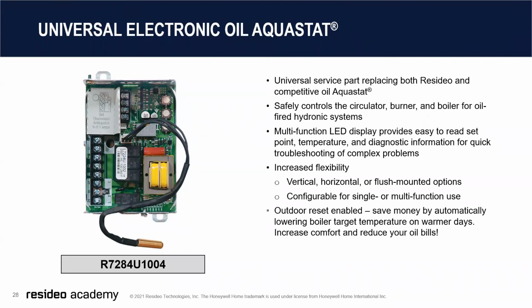So safely controls the circulator, the burner, and the boiler for oil-fired hydronic systems. Multifunction LED display provides easy to read set point, temperature, and diagnostic information for quick troubleshooting of complex problems, as well as it's really easy to set up because of that little display. Increased flexibility. You can do vertical, horizontal, or flush mount. It's configurable for single or multifunction use. As you can see on the board there, it's got a couple little holes that you can poke the sensor through so that you can, again, have a little bit of flexibility as to how you're mounting it to the boiler. It does have outdoor reset enabled, which is becoming code for more and more areas, that AQUASTATs have some ability to do a setback on warmer days, which also helps pass along savings to the customer.